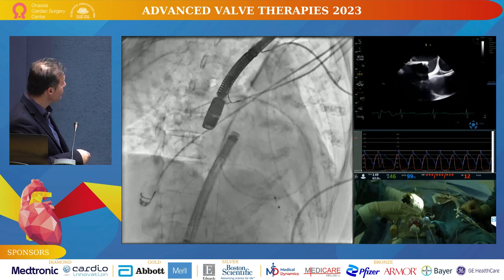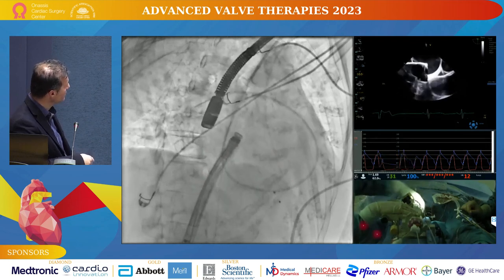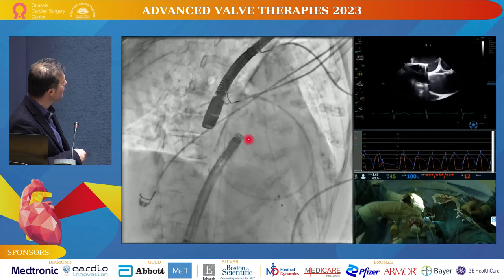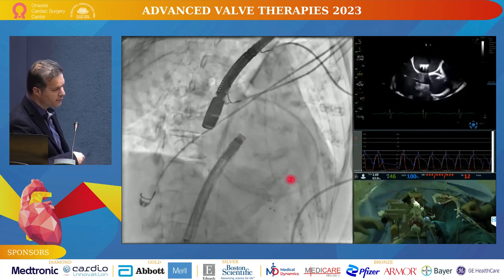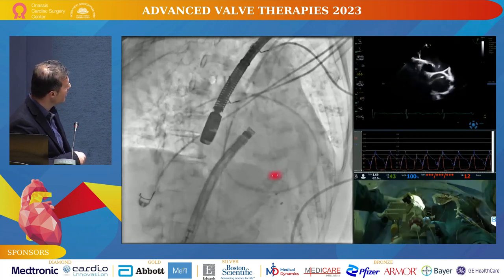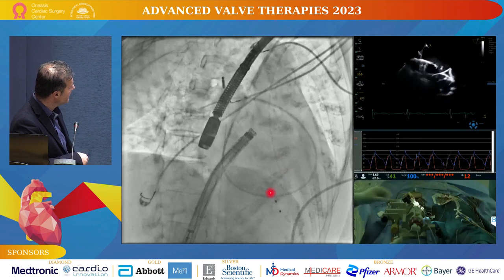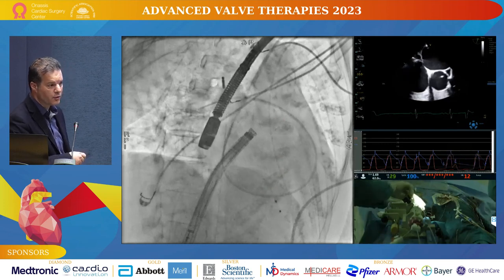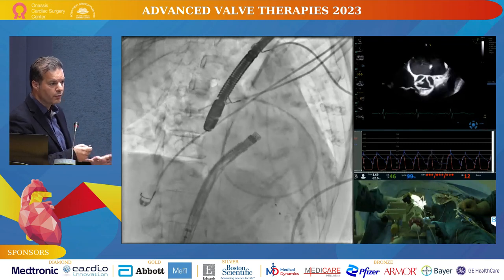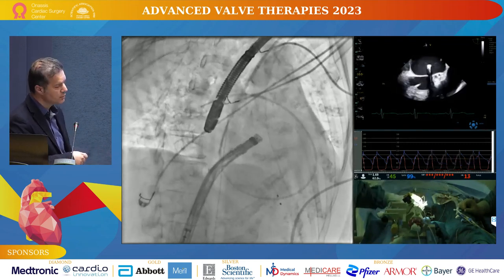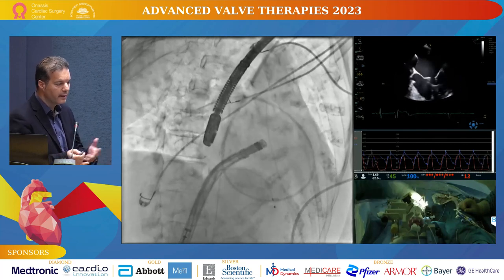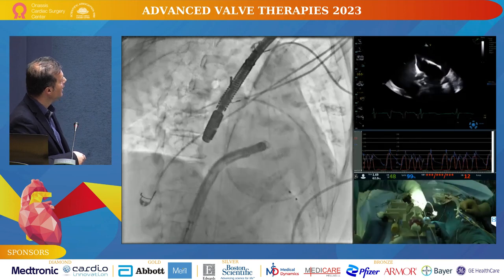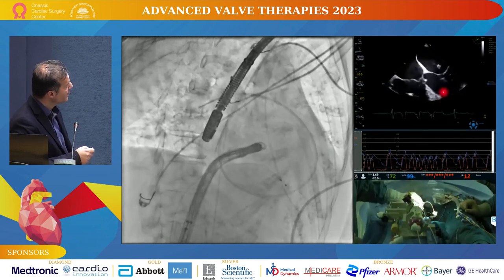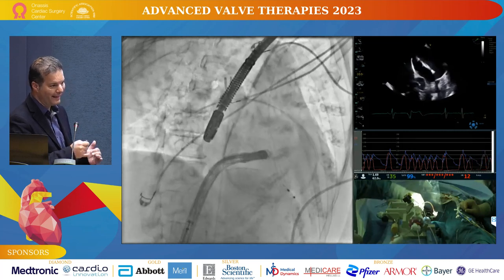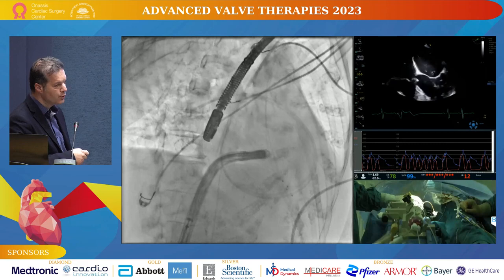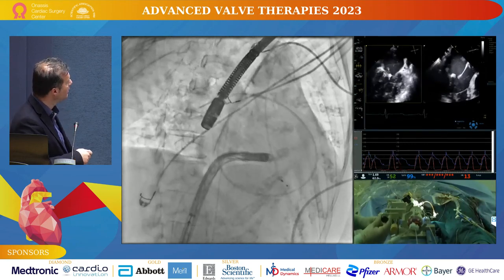So now the plan will be to bend this system down to the mitral valve. You can see we flex the catheter and we bend down to the mitral annulus. We work in a pre-specified view, an RAO cranial usually, or RAO caudal, depending on the CT scan. You would expect the annulus to be around here. If there is some calcification of the annulus, this is great news because you have a fluoroscopy marker. But in this case, there wasn't. So this valve is meant to work both for calcified annuli and for non-calcified annuli. We observe, of course, the flexion of the catheter on the echo. So the echo is our eyes again. It's very important to emphasize that. And we use 0 contrast for this implantation.